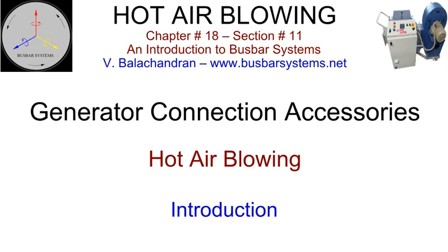Generator connection accessories. Hot air blowing. Introduction. Hot air blowing is resorted to prior to bringing an enclosed busbar system back into service, after it had remained in a de-energized condition for a significantly long time.